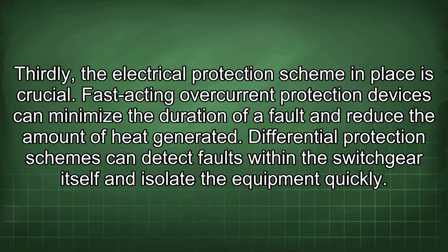Thirdly, the electrical protection scheme in place is crucial. Fast-acting overcurrent protection devices can minimize the duration of a fault and reduce the amount of heat generated. Differential protection schemes can detect faults within the switchgear itself and isolate the equipment quickly.